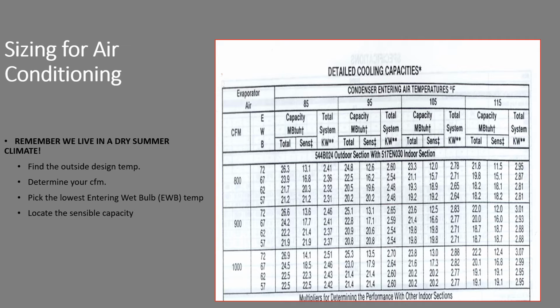And then you locate the sensible capacity. This manufacturer showed sensible capacity in a different table. So please notice here at 72 degrees entering wet bulb, the sensible capacity is only 13,000 BTUs per hour. The total capacity is 26,000 BTUs per hour. The difference is all tied up in latent capacity, in removing and turning that humid, muggy air in the form of vapor into water. At a 62-degree entering wet bulb, it's almost identical. By the time you get down to 57, it is identical, meaning the capacity of that machine is all sensible and it's available to lower the temperature of the air as it goes through the coil.